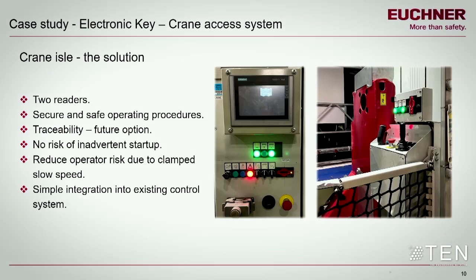For the crane access, so we've already made the request to enter that particular aisle. We've pulled our RFID key out of its reader. We've unlocked the door. We've entered the area. We've closed and locked the door behind us so no one else can follow me in. I then transfer that key into two parts of the system. Okay, so there's two readers, one on the front and one that enables joystick controls. So if a product's fallen over in my huge logistic center aisle, I can move the crane to go and locate it. I'm not climbing over racking, putting myself at risk. I'm using the crane itself to do that.